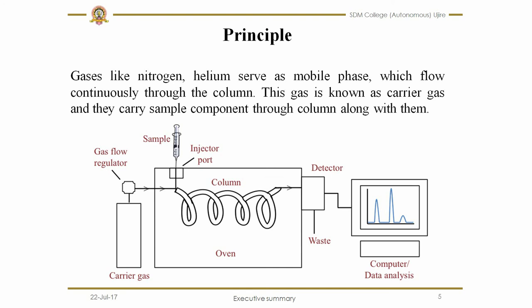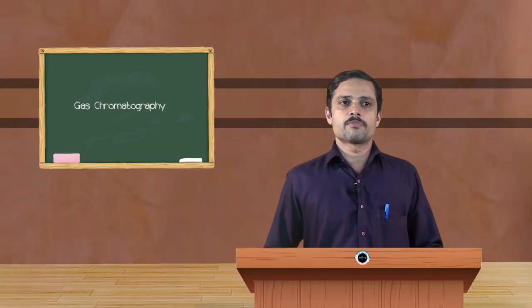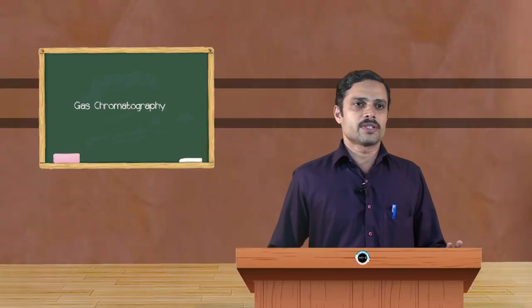It may be flame ionization detector or thermal conductivity detector, and that detects the signal. It will then be processed through a computer or data analyzer where we will get the graph of percentage of abundance against time. First, the carrier gas is started to flow through the oven and oven is preheated to the respected temperature, maybe more than 100, usually 150 degrees Celsius.